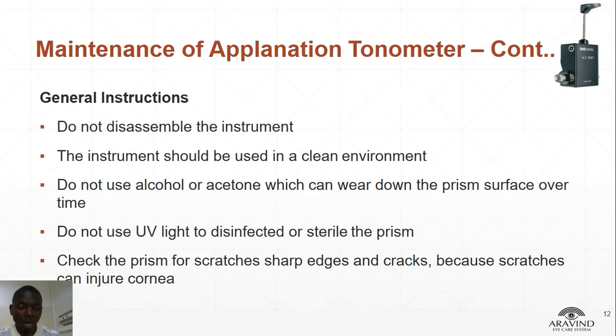Do not use alcohol or acetone, which can wear down the prism surface over time. Do not use UV light to disinfect or sterilize the prism. Check the prism for scratches, sharp edges, and cracks because scratches can injure the cornea of the patient.